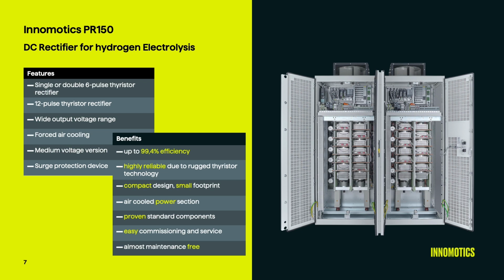What are the features of this product? We can offer it as a single 6-pulse thyristor rectifier, or in parallel connection we have two 6-pulse rectifiers, and another version could be a 12-pulse rectifier, depending on the power rating, on the voltage rating, whatever the customer is requesting. Interesting in that product is that we have a wide voltage range. Different electrolyzer stacks might have different voltage requests, so we are able to deliver in the low voltage area as well as in the medium voltage area, and we are able to deliver DC voltages higher than 1500 volts. We don't need an additional water cooling system. Our system is just a forced air-cooled one. We can see there's a fan on top. This is good enough to cool the semiconductors, even for such high power ratings.